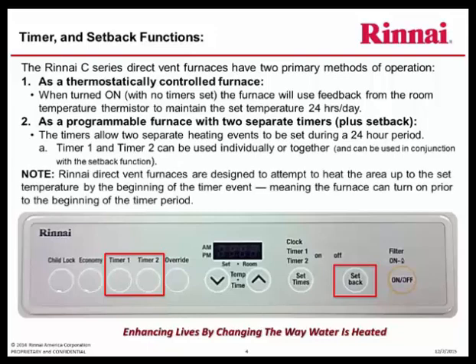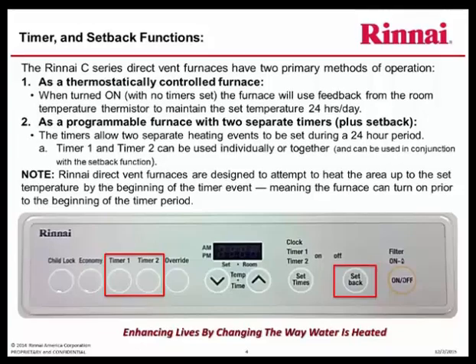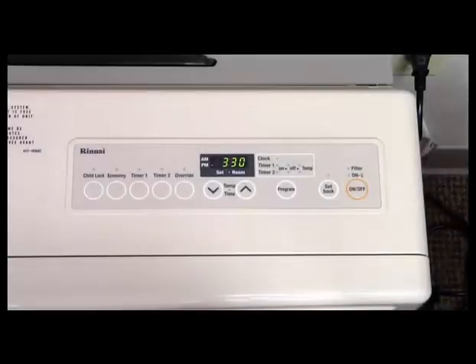Note: Rinnai direct vent furnaces are designed to attempt to heat the area up to the set temperature by the beginning of the timer event, meaning the furnace can turn on prior to the beginning of the timer period. The clock must be set before you can set or use the timers.